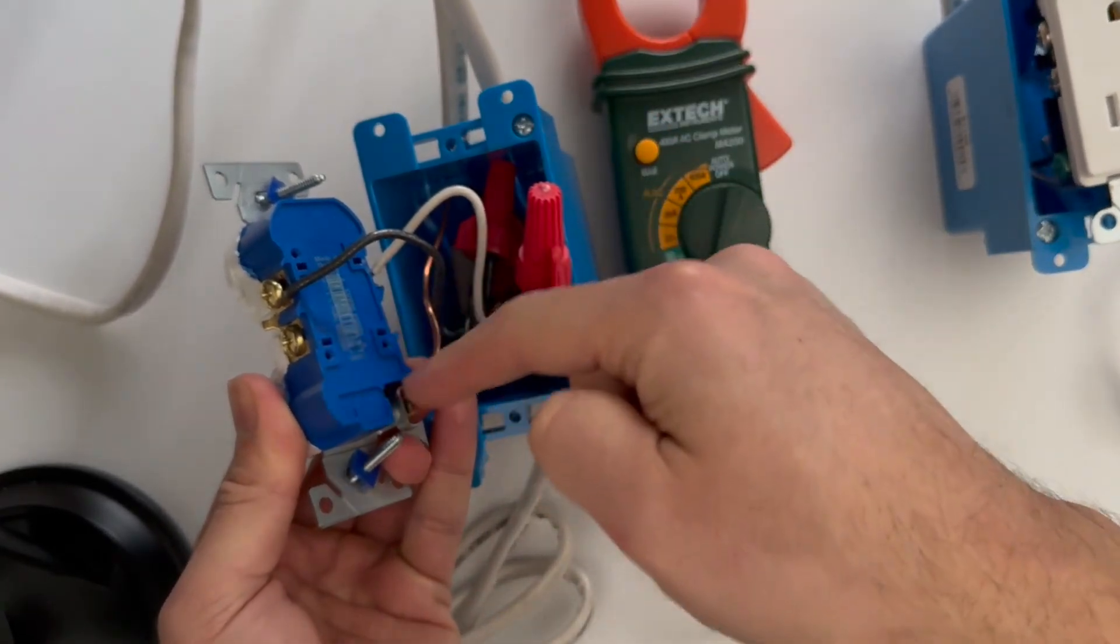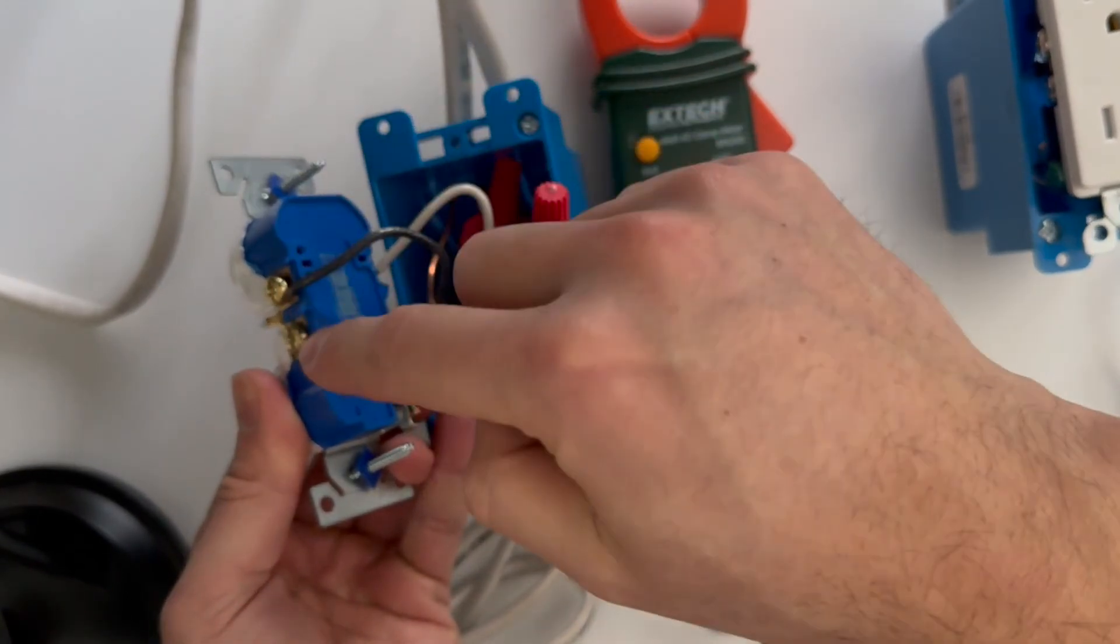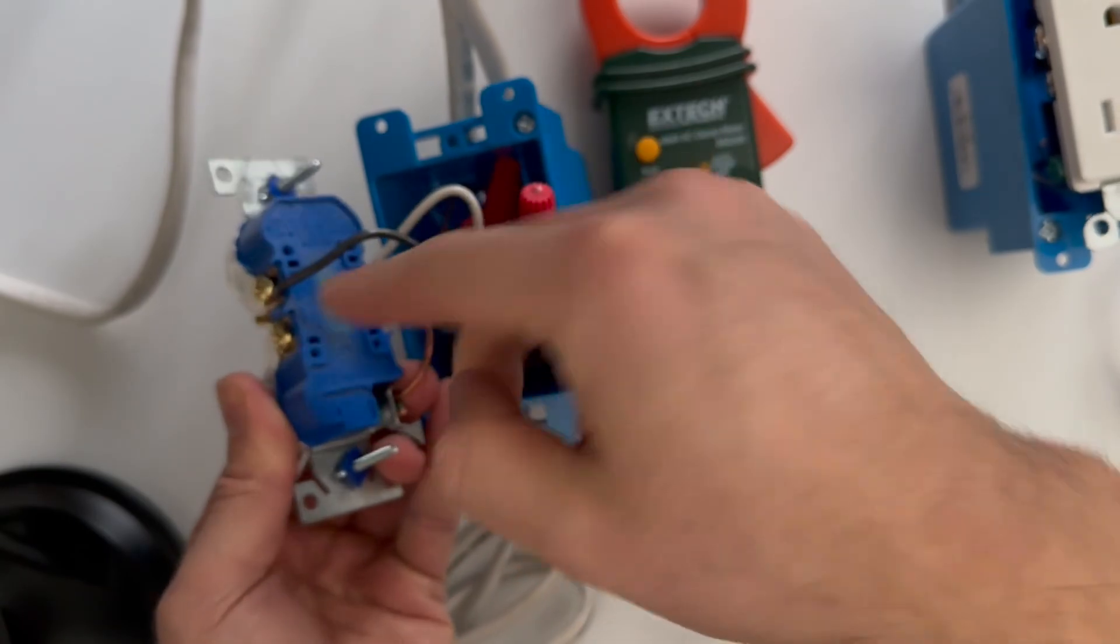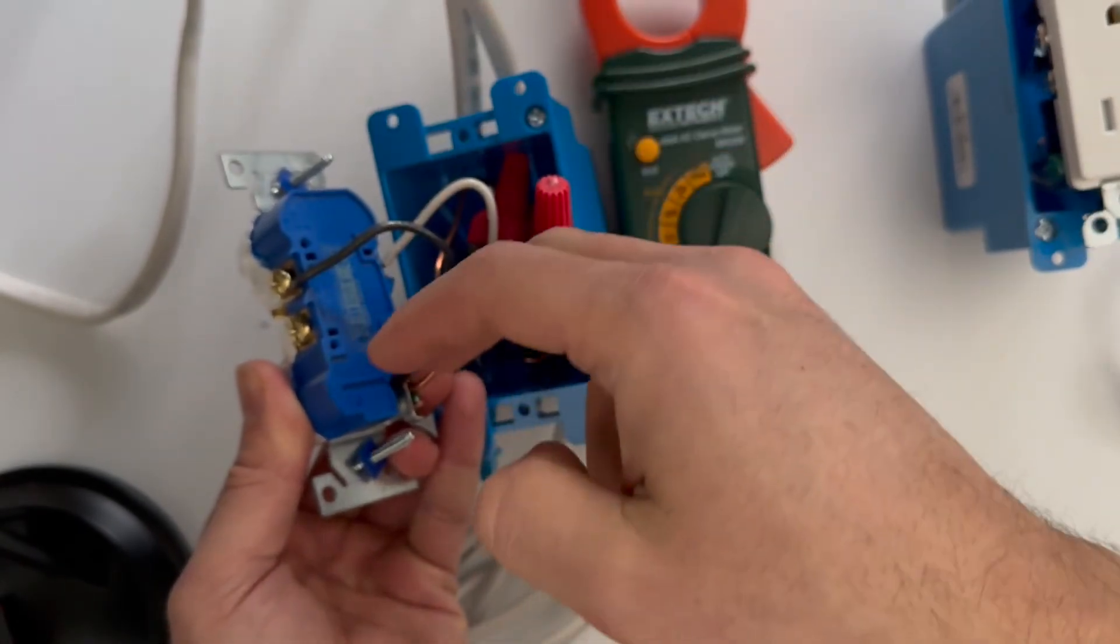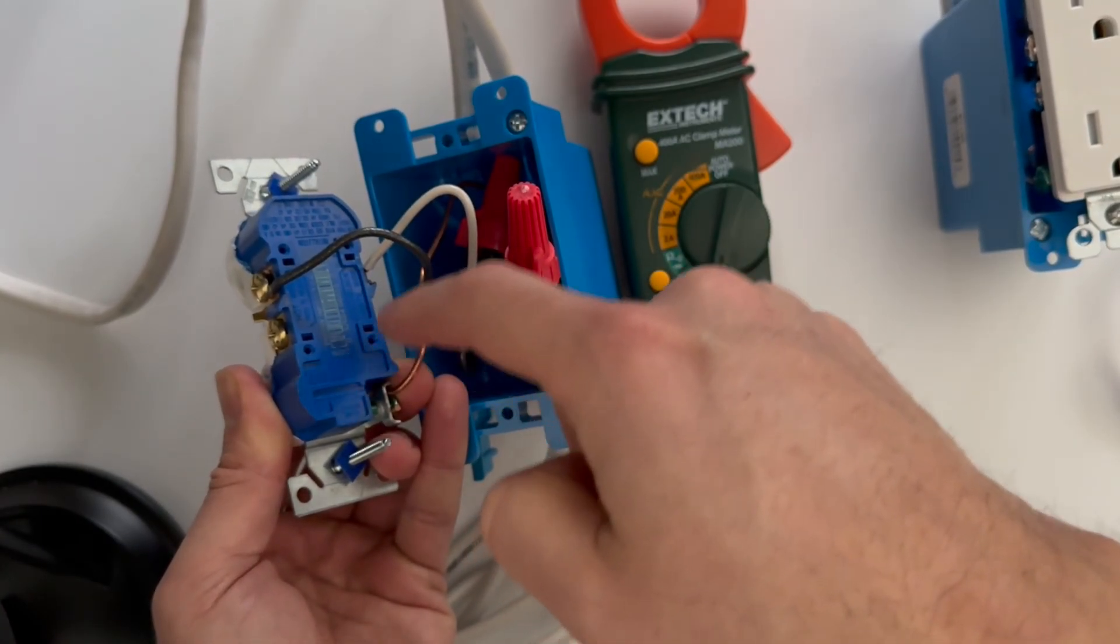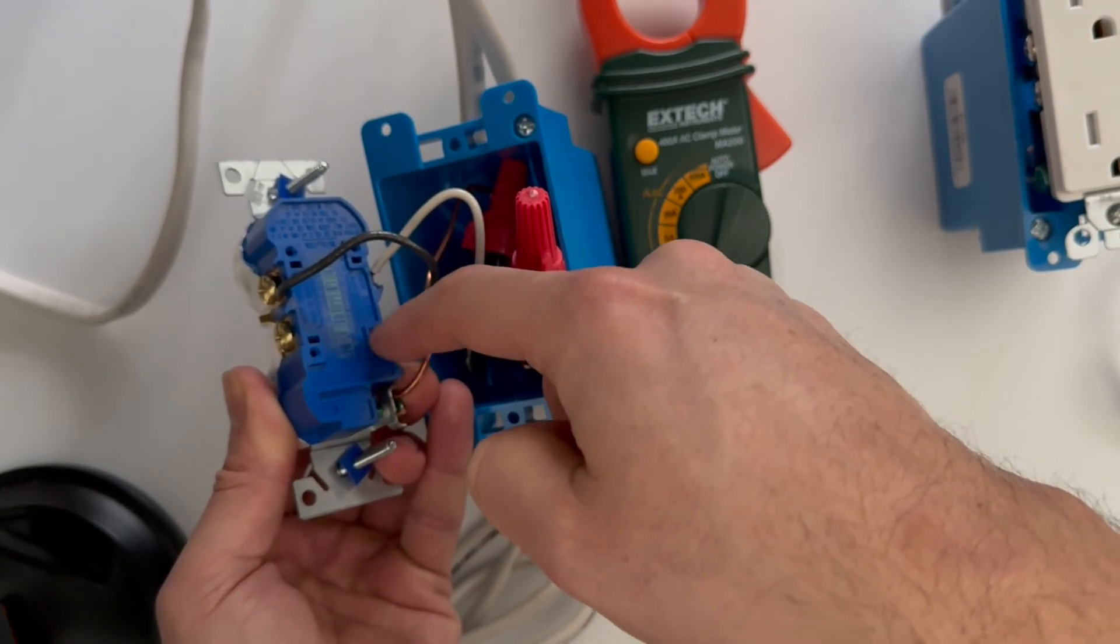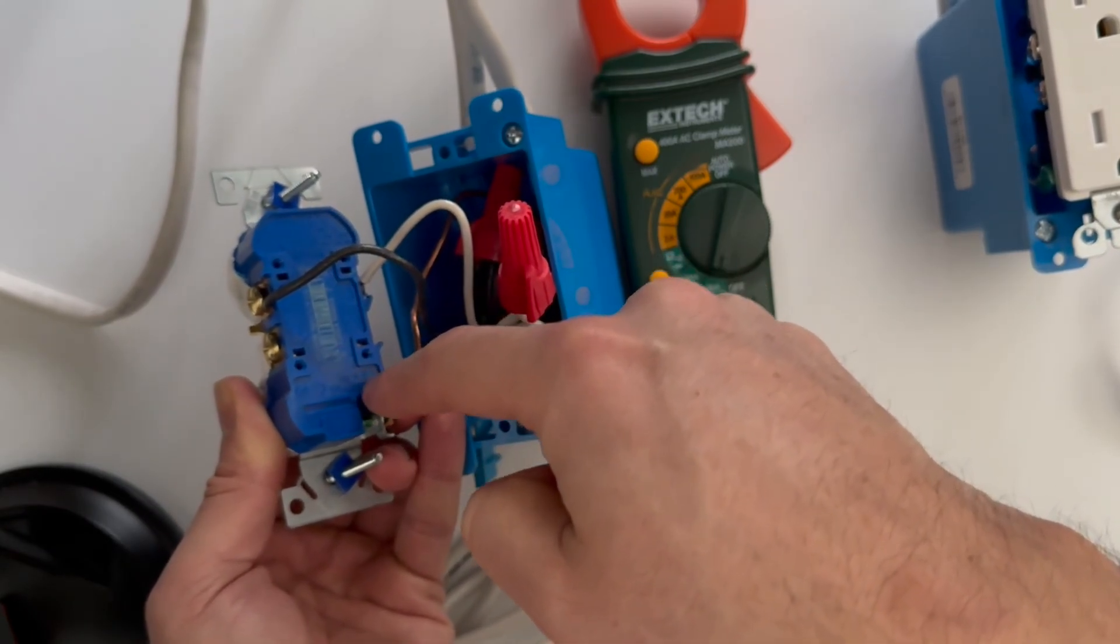Sometimes you will see an outlet can actually have four pairs of wire. You could have two backstabbed hot wires, two side-mounted, and then you will have four other neutrals here. One could have been loose here too.